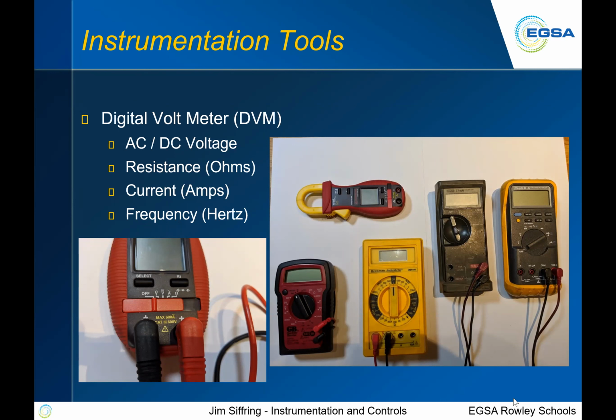So what do we look at with a digital voltmeter or digital multimeter? We look at AC and DC voltage, resistance in ohms, current, which reads out in amps typically, and frequency in hertz. And what I find is this amp clamp in the main picture there, the one with the red meter with the yellow loop on it, is a clamp-on ammeter with a multimeter built into it. That's the one I keep in my truck, as a matter of fact. You can go down to Home Depot or Grainger and buy those for less than $100 with a set of leads and a case. Very powerful tool, pretty simple, very durable. They'll live in the trunk of your car or behind the seat of your truck for years.